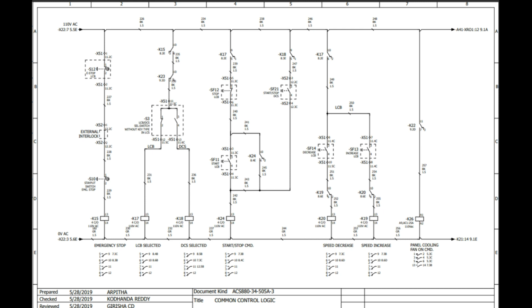Next, if you want to run the drive from control mode or PLC mode, then K18 has to get high and will come to the fourth tapping. K18 will get NC, and this command, the dotted box command, start stop DCS, X52, channel number 3 and 4. This command will be continuously NC, and this supply will come from the PLC, and the K24 auxiliary contactor will be healthy and the drive will continuously run.